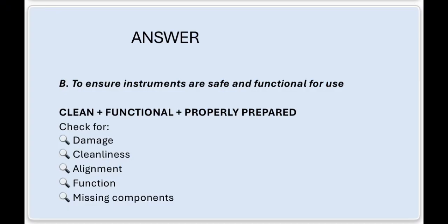The correct answer is B, to ensure instruments are safe and functional. Sterile does not automatically mean functional. An instrument can be clean and even sterile, but still be damaged or unsafe. Technicians should inspect instruments according to their design and intended function.